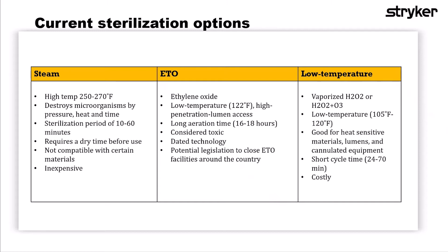ETO is a dated technology and there is potential legislation throughout various states to close down ETO facilities. Low temperature vaporized hydrogen peroxide — which can be combined with plasma, ozone, or used singularly — operates in the low temperature range of about 105 to 120 degrees. It is excellent for heat-sensitive materials, lumens, cannulated equipment, and the intricate high-technology equipment that cannot go into steam.